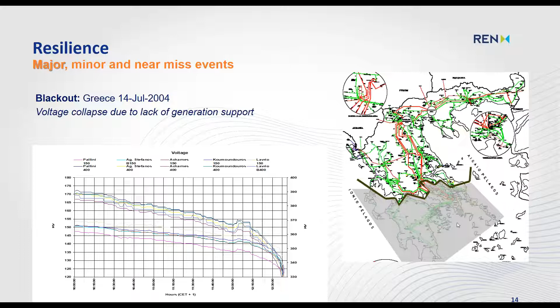So in this case, this phenomenon was accelerated because of the loss of the 1,700 megawatts of distributed generation. The other one in 2004 was a voltage collapse, not a frequency issue, and this was in July 2004, just before the Olympics in August in Greece. It's a slow phenomenon, but they were unable to keep the voltage on the system, and then the system collapsed.